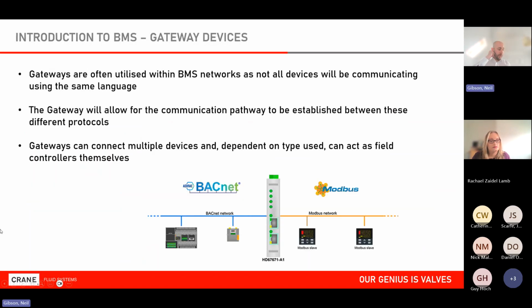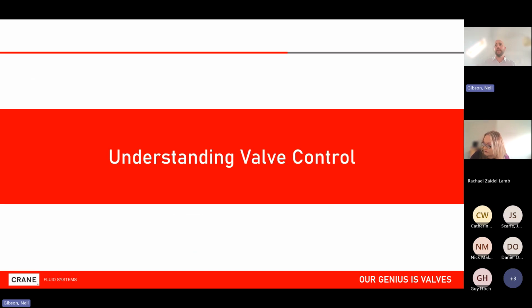Talking about Modbus and BACnet, one of the key questions we get is, what if I have a BACnet system and someone's trying to sell me a Modbus device? How do I integrate the two? And we simply explain you use a gateway, a translator. So you can have a series of Modbus field devices on a floor, and then connect them into your BACnet network without any real issue or challenges. So you can integrate these two open protocols together fairly seamlessly.